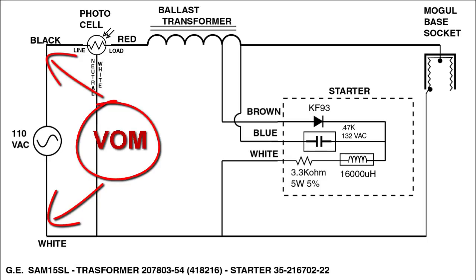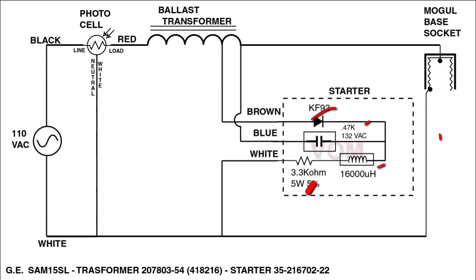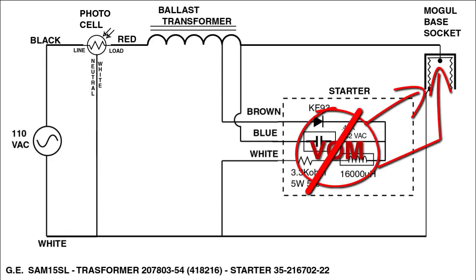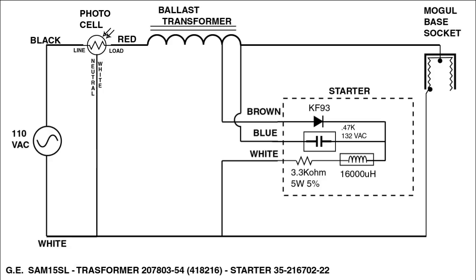While troubleshooting in the field, you can only really measure the voltage at the input terminals to the fixture. If you attempt to measure across the lamp terminals, the voltage spike may damage your meter. If you have input voltage, then a thorough physical inspection on the bench and swapping in known good parts are your only recourse.